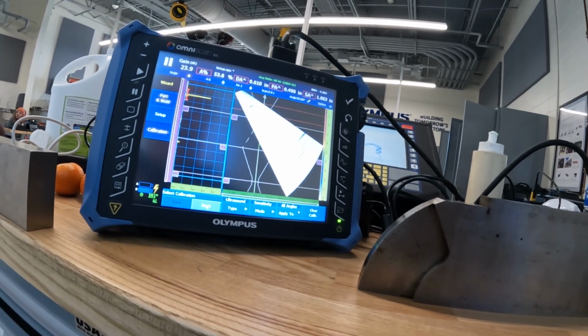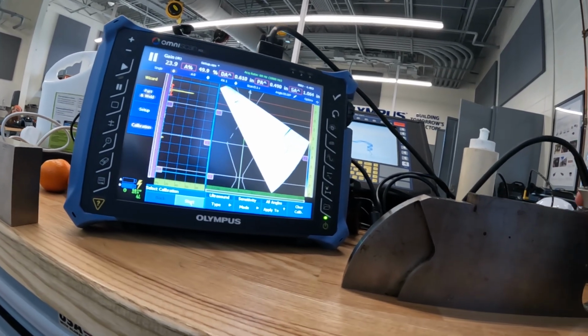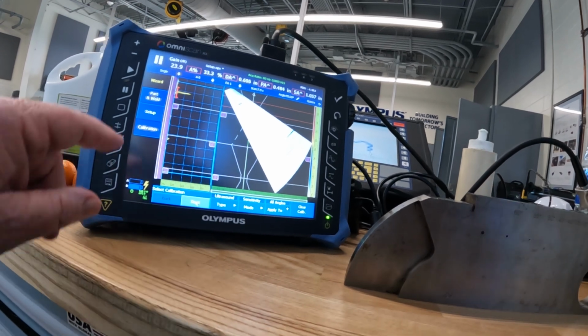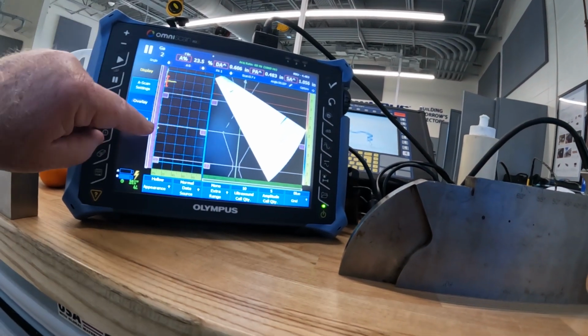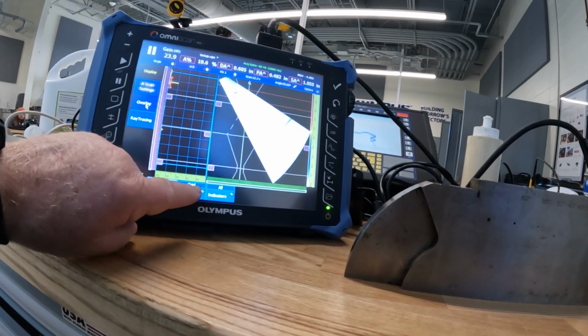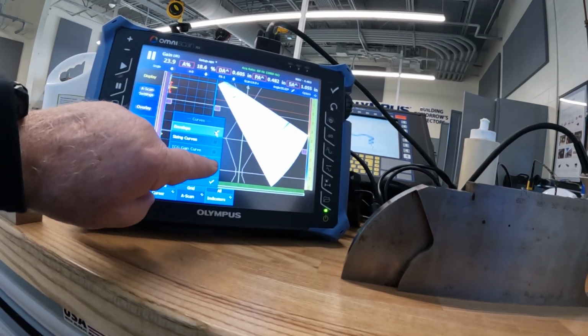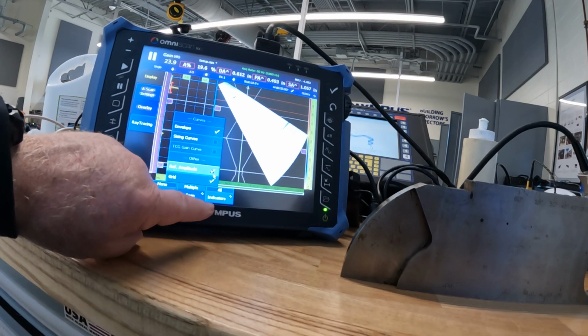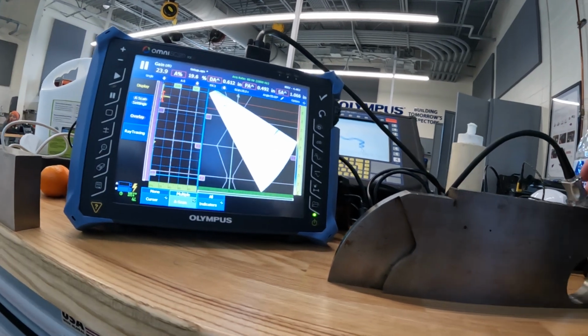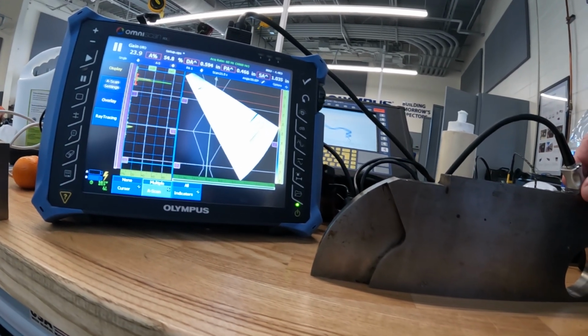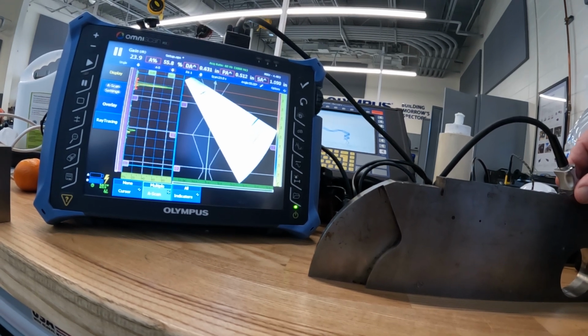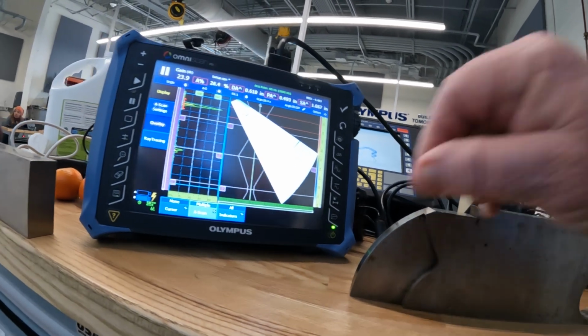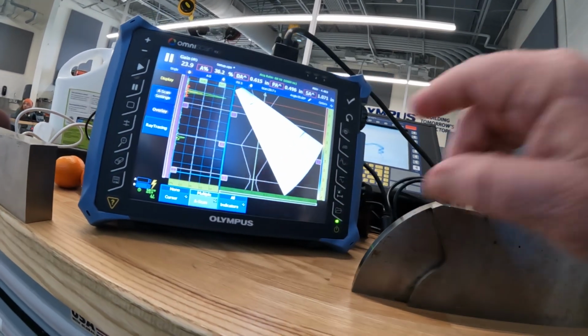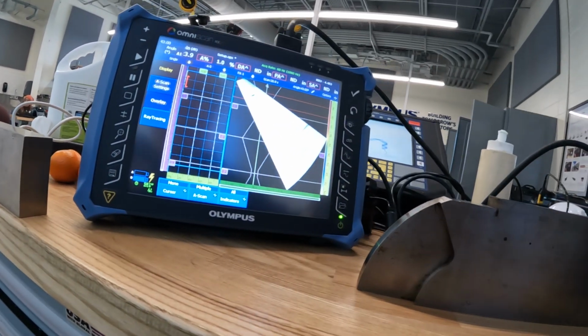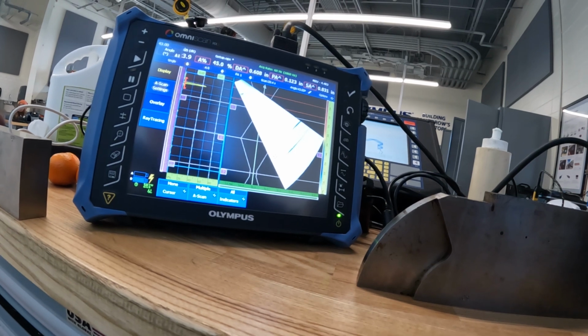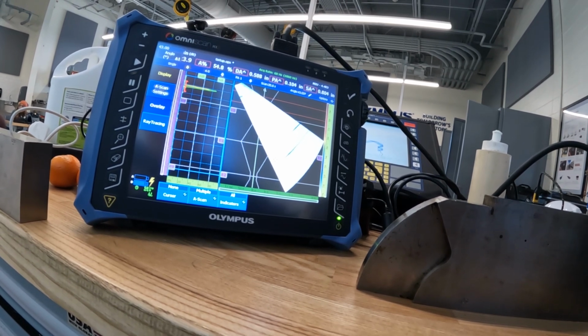So now, how do you test to see if it's good? Well, I should be able to peak and I should get a maximum of 80%. I'm going to turn on my display. Be sure my overlay is on. Under this, I'll make sure envelope and my reference amplitude is on. So when I come back, I want to verify that my response is not going over 80. You can see it's going up to the reference line. If I change the angle, it should also be in this range. It should go up to my 80%.